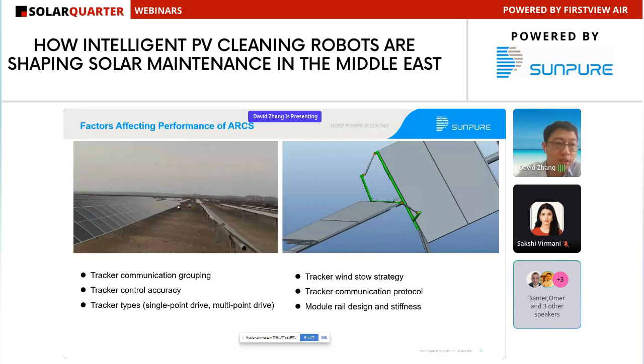The second factor is tracker control accuracy. This is also related to the angular difference of tracker rolls, because if the tracker's cleaning angle is designed to be 30 degrees but the actual angle is 35 degrees, you can imagine how different that is between the design and the actual outcome. This will also reduce the performance of the trackers.